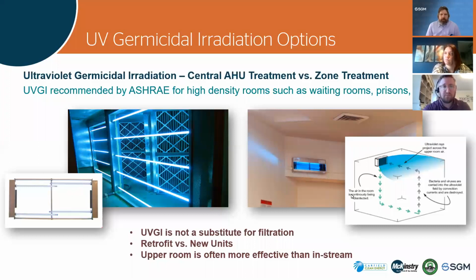Like you said, Brian, the UV is hard to retrofit to existing equipment, but one of the examples recently on some hospitals that we've been dealing with, our rooftop units are being manufactured and then sent to a specialty area to have UV packages retrofitted right to the brand new rooftop unit. And what that specialty UV section does is it meets the design of the volume of air, the CFM, and also the speed or velocity, the feet per minute, of the air going through that rooftop unit. And then that rooftop unit is delivered on site and put on a brand new building. So when it's designed with the manufacturer, it doesn't affect warranty on the rooftop unit.